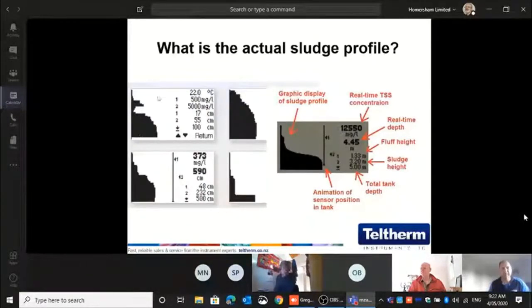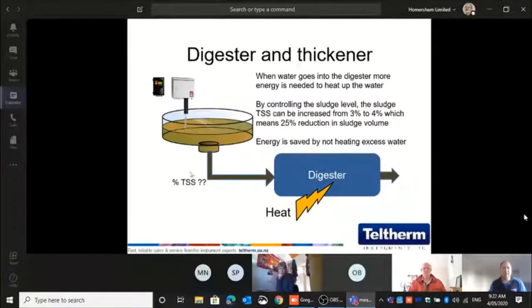In your SCADA system, you can actually create this. New Plymouth did a very good job of showing this on the screen as well while the sensor goes down. This is basically what you want, but if you've got this, an ultrasonic will have an issue here, because it will see this layer, not the actual layer. So there's a few things. A lot of things you can see that the unit will give you. So a lot of detailed information.